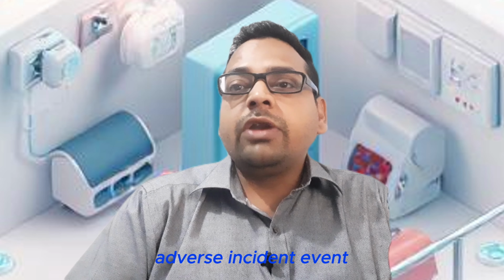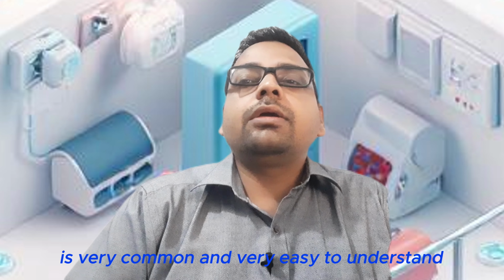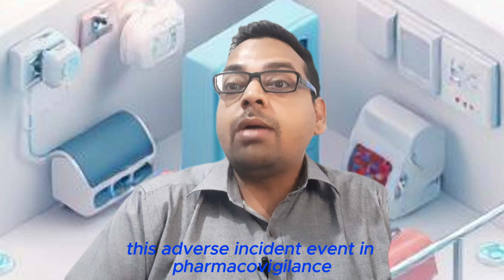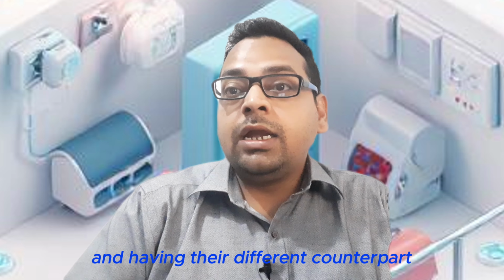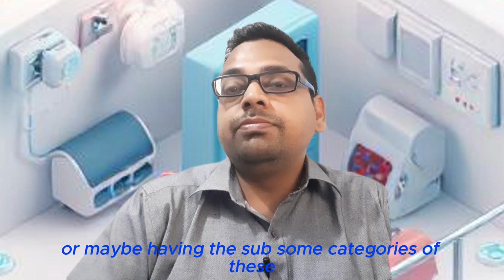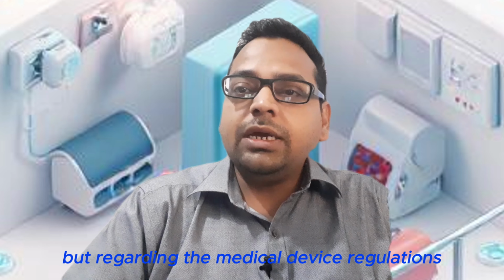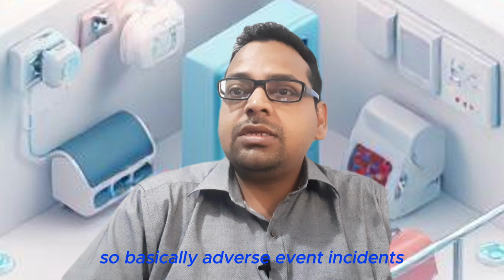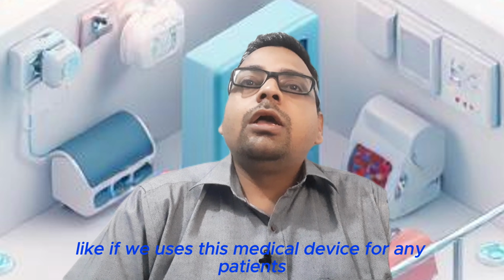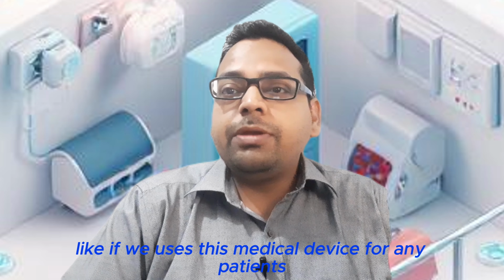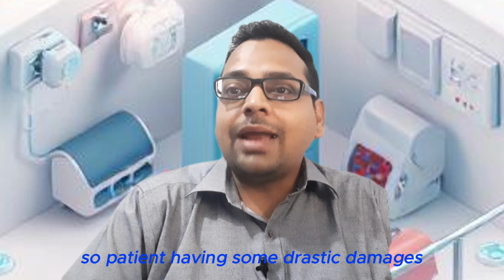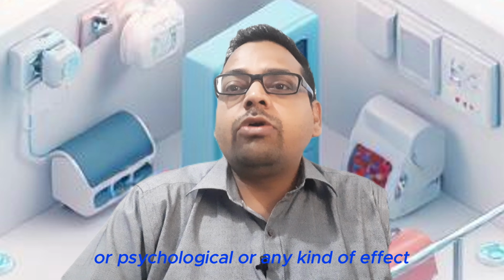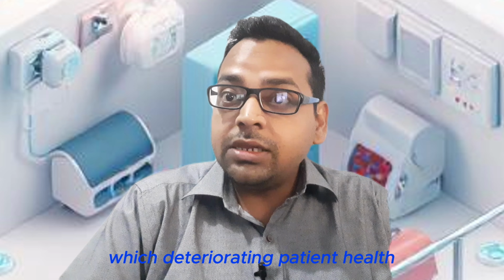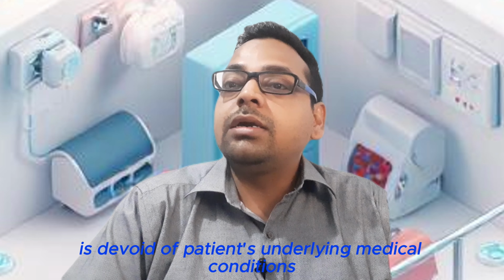The terminology adverse incident event is very common and easy to understand, but at the same time, in pharmacovigilance it has different meanings and different counterparts, or maybe subcategories. But regarding medical device regulations, what is an adverse incident event? Basically, adverse incident events are associated with a medical device. If we use this medical device for a patient, and the patient suffers some drastic damaging, psychological or other effect which deteriorates the patient's health, but that deterioration is devoid of the patient's underlying medical conditions.